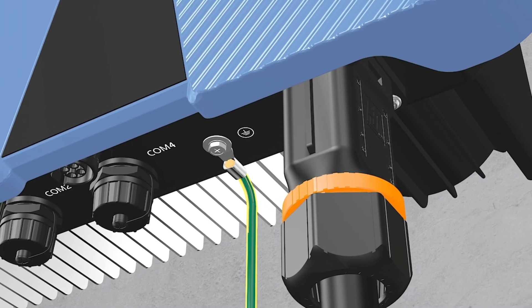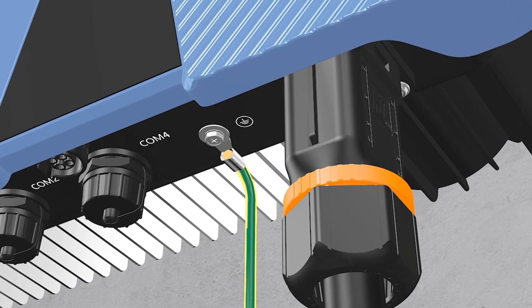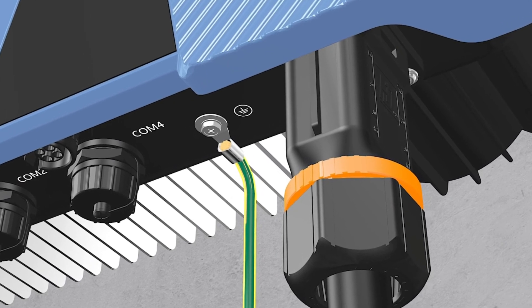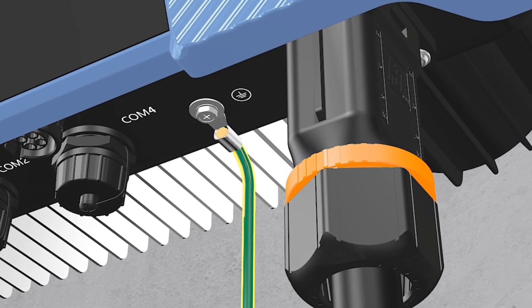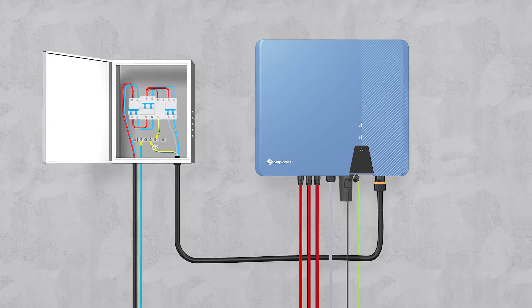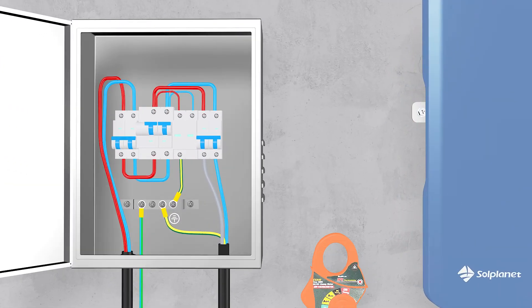Check the P-E connection with the multimeter. Make sure that the inverter's exposed metal surface has a ground connection.